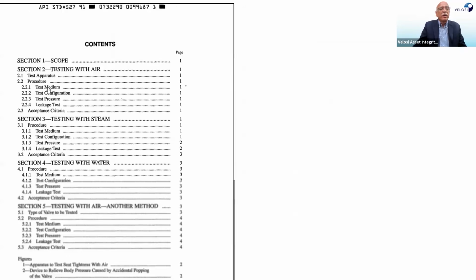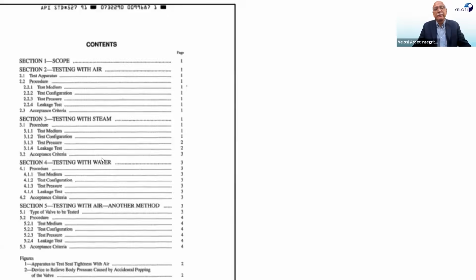Then this is also about seat tightness of pressure relief valves, and it covers mostly, if you see it, testing with air, how a valve can be tested with steam, testing with water, testing with air and other methods. So this is how the PSVs could be tested.